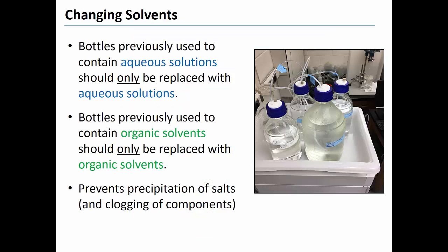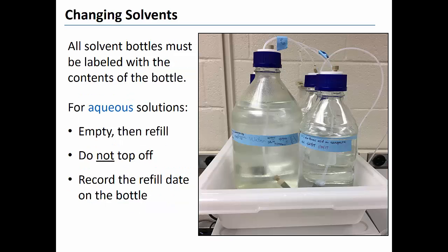When changing solvents, bottles that were previously used to contain aqueous solutions should only be used to contain aqueous solutions. Similarly, bottles previously used to contain organic solvents should only be used to contain organic solvents. This approach helps to prevent the possible precipitation of mobile phase additives such as buffer salts. The contents of a solvent bottle must be completely and clearly labeled on the bottle. Keep in mind that aqueous solutions can rather quickly become contaminated with bacteria and algae when stored for more than a few days at room temperature.